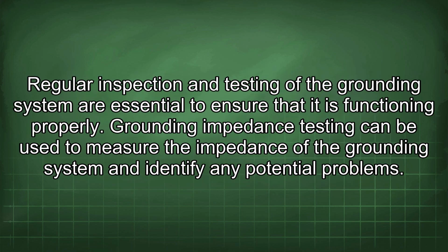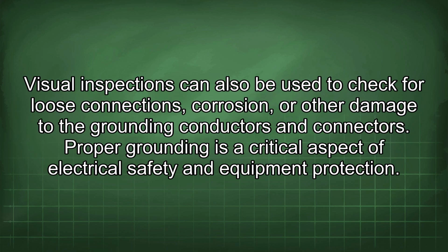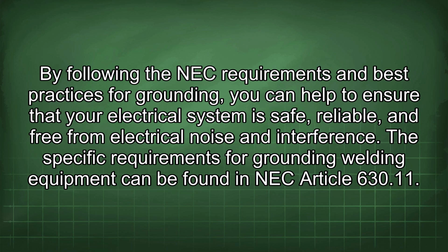Regular inspection and testing of the grounding system are essential to ensure that it is functioning properly. Grounding impedance testing can be used to measure the impedance of the grounding system and identify any potential problems. Visual inspections can also be used to check for loose connections, corrosion, or other damage to the grounding conductors and connectors. Proper grounding is a critical aspect of electrical safety and equipment protection. By following the NEC requirements and best practices for grounding, you can help to ensure that your electrical system is safe, reliable, and free from electrical noise and interference.